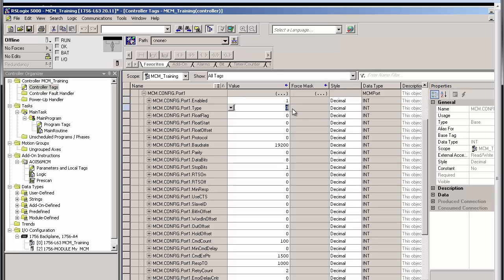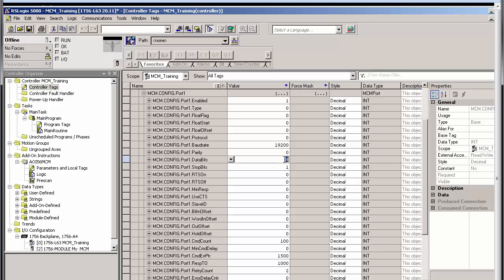Next, with type set to 0, the port will be a Modbus master. Entering a 1 here would set the port as a slave. Next, I'll set the baud rate to 19,200, parity to 0, data bits to 8, and stop bits to 1. These settings must all match those of the slave devices on the Modbus network that you'll be connecting to. And I can now begin adding Modbus master commands.